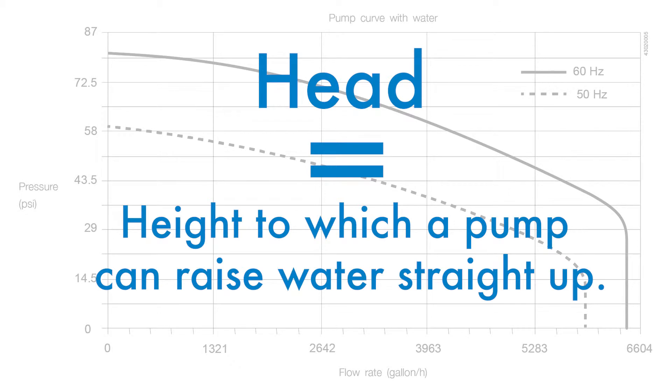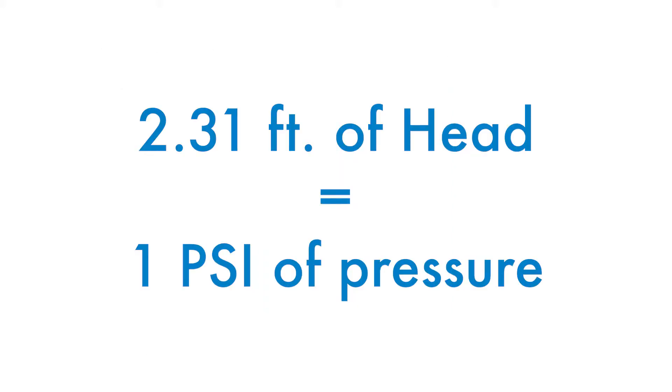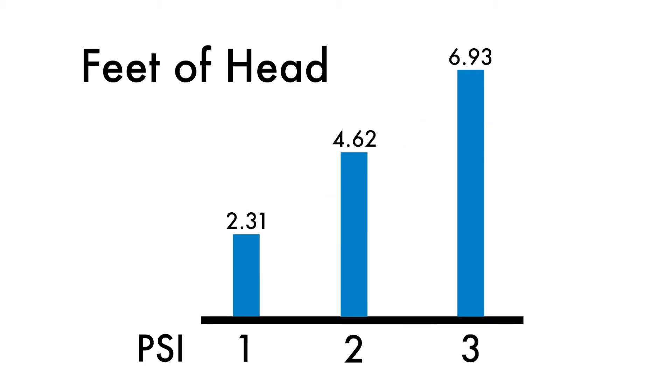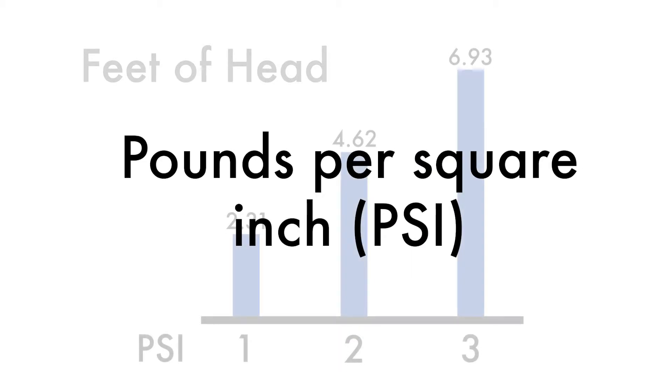Head is the height to which a pump can raise water straight up. Water creates pressure or resistance at predictable rates. For example, every 2.31 feet of head equals 1 psi of pressure. Common units for indicating pressure are feet of head and pounds per square inch.